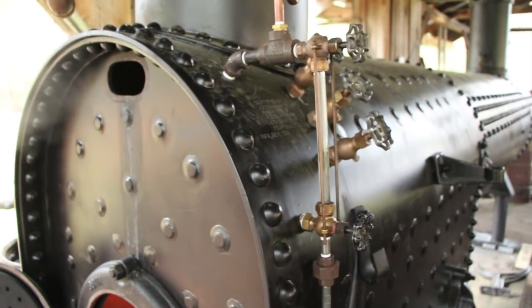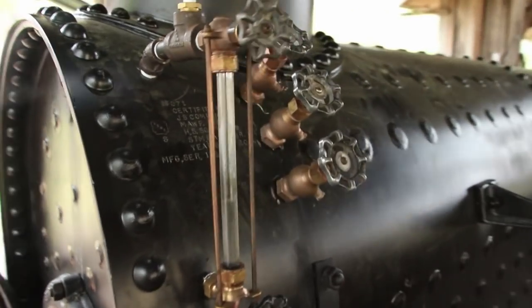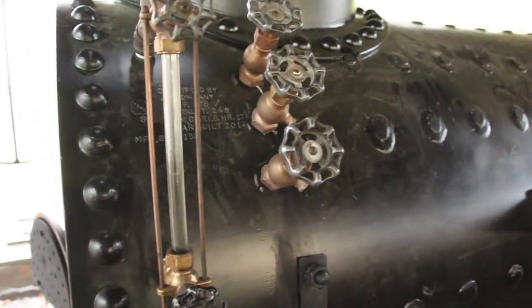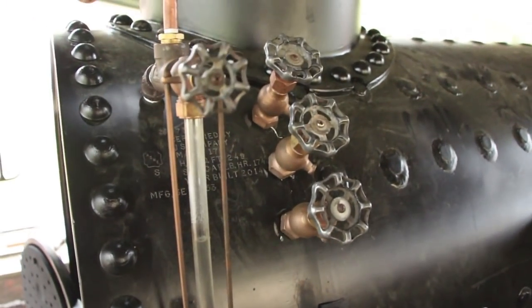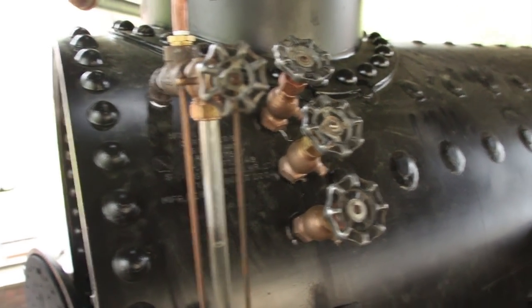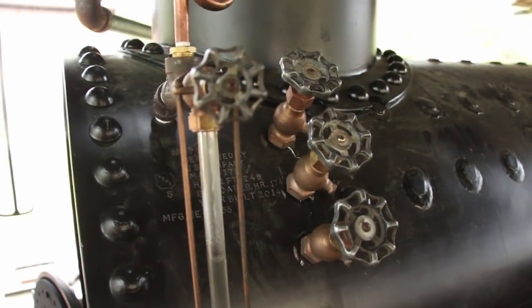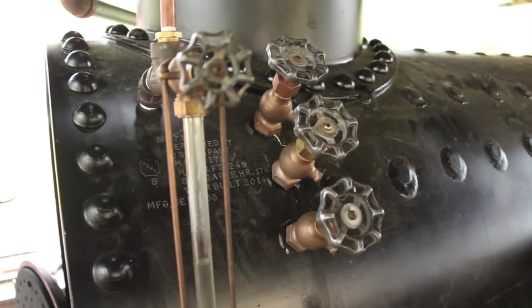There are two valves above and below the sight glass — should that glass break, you can shut those valves and that will shut the steam down. And behind it you see three other valves there. Those are called try-cocks — T-R-Y-cocks — and they're for trying out to see where the water is. This is just a manual way of seeing the water level in the boiler. You can open those valves up.